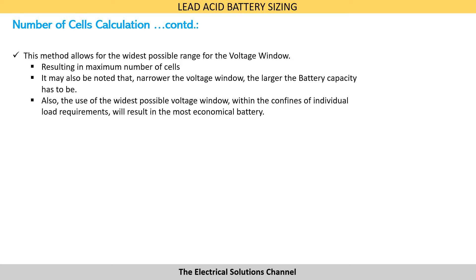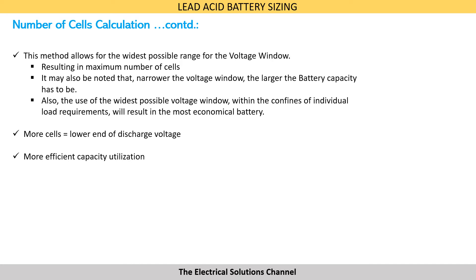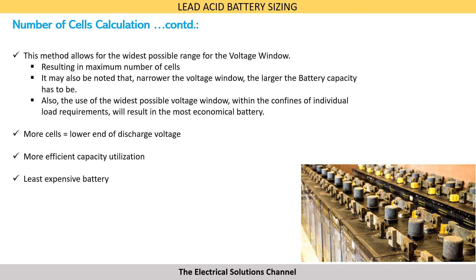This results in the maximum number of cells. It may also be noted that narrower the voltage window, larger the battery capacity has to be. Also, the use of the widest possible voltage window within the confines of individual load requirements results in the most economical battery. More number of cells result in a lower end of discharge voltage, allowing for more efficient capacity utilization and the least expensive battery.